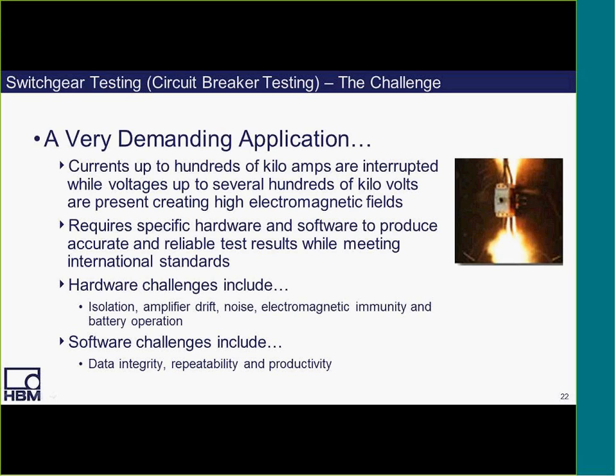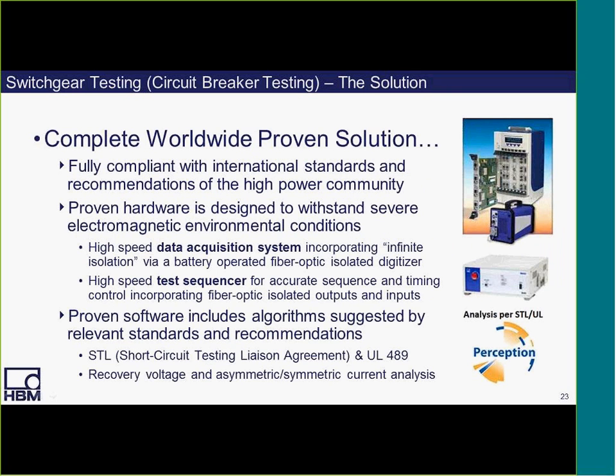It's a very demanding application because here you've got currents up to hundreds of kiloamps which are interrupted, while voltages up to several hundreds of kilovolts are present, creating high electromagnetic fields. So this is going to require specific hardware and software to produce accurate and reliable test results while meeting international standards. So the hardware challenges include isolation, amplifier drift, noise, electromagnetic immunity, and battery operation. Software challenges include data integrity, repeatability, and productivity.